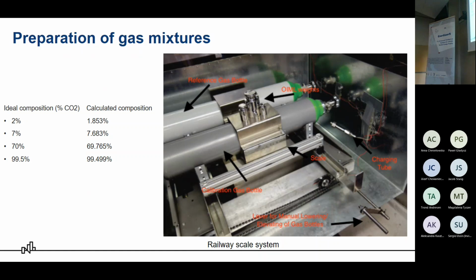We prepared 4 mixtures: 2% of CO2, 7%, 70%, and 99.5%. We had a plan to prepare 5 mixtures, but unfortunately we had a CO2 leakage in the weighing chamber, so we had to postpone the fifth mixture. But I hope that SINTEF will prepare it later. For this case, we used a specially designed railway scale system, where 2 gas bottles are allocated.